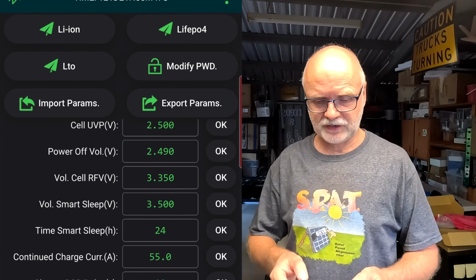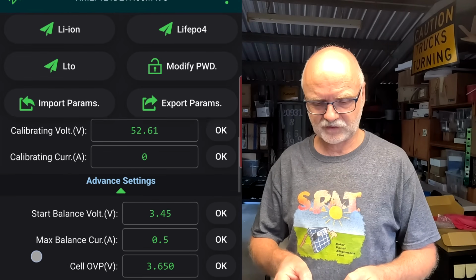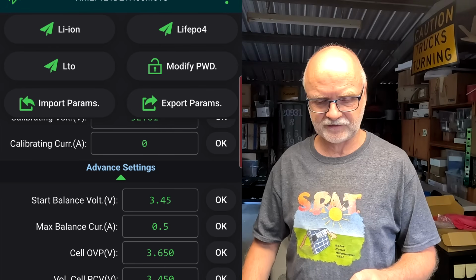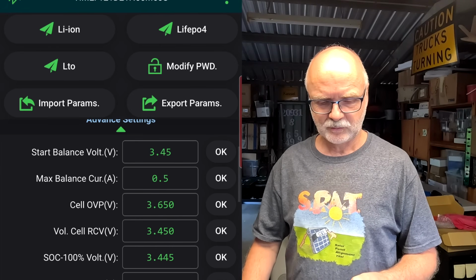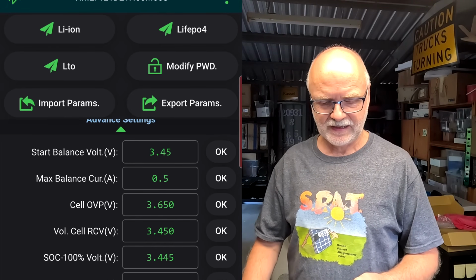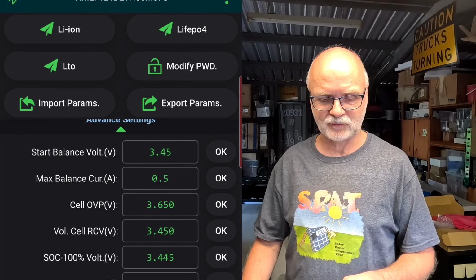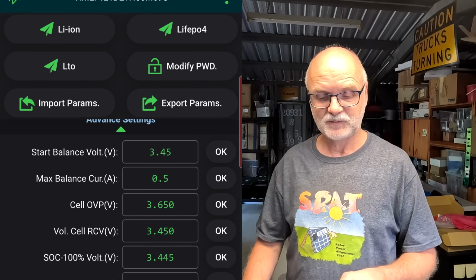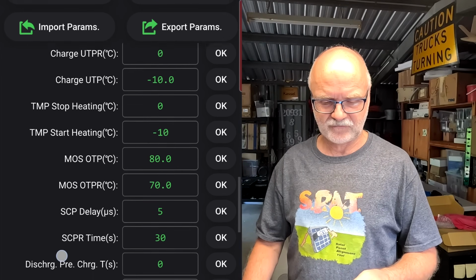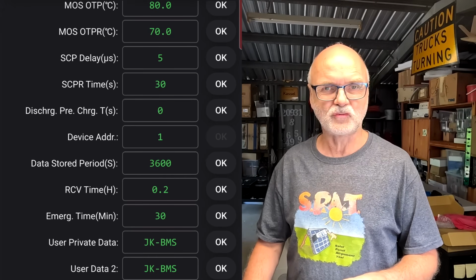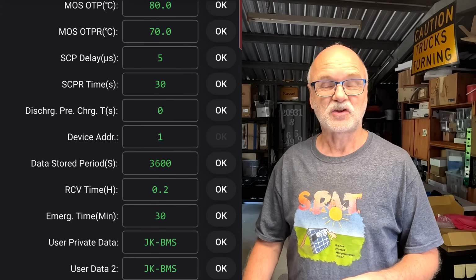All right, let's have a look here in the settings. What is going on? 3.45 volts is the balance start voltage. Perfect. We are charging to 3.45, and the reset occurs at 3.445 times 16, if we wait for 0.2 hours, 12 minutes.